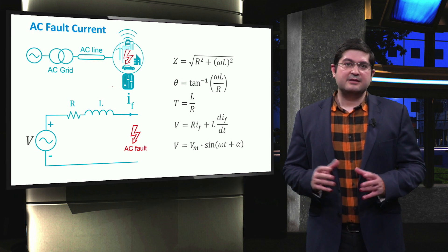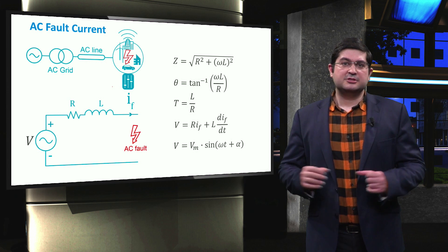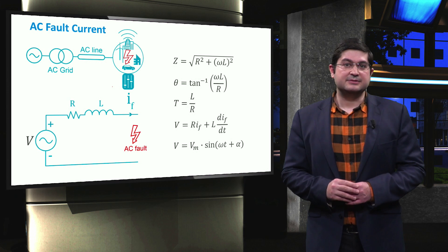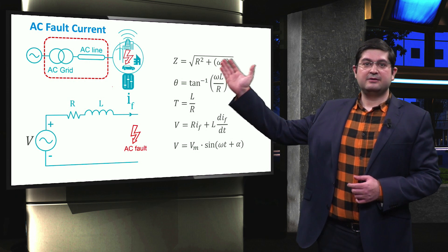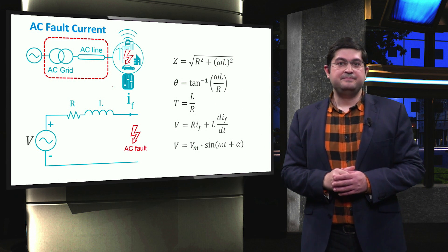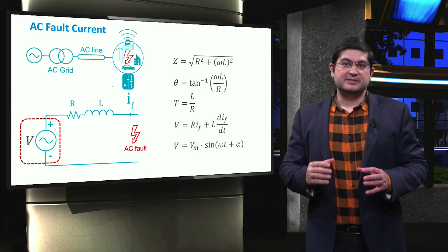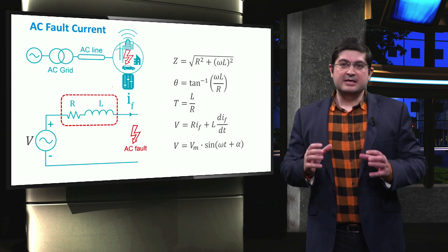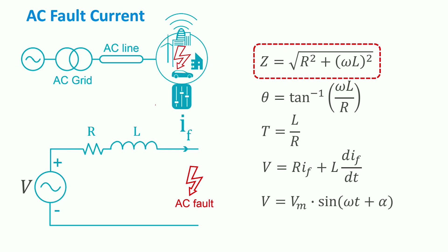If the fault occurs inside an AC microgrid which is connected to the external grid, it is likely that a large portion of the fault current is fed by the AC grid. The external grid is connected through a transformer and a line to the AC microgrid. The equivalent electrical circuit shows the grid represented by a voltage source, where the impedance of the line is represented by the resistance R and the inductance L. The amplitude of the impedance Z depends on the resistance R and the reactance, which is equal to omega multiplied by the inductance L.